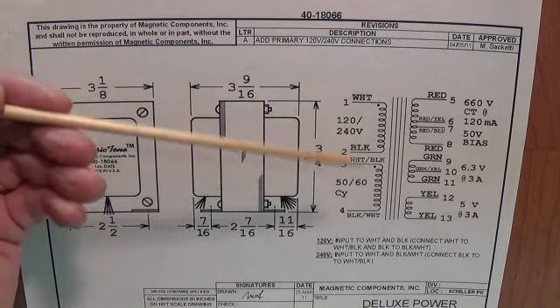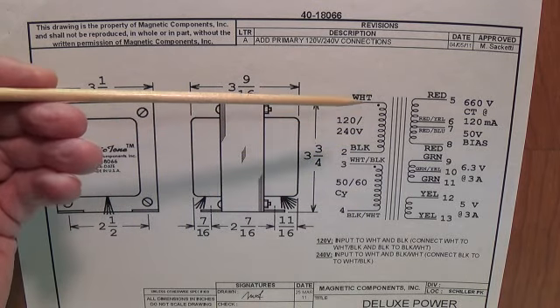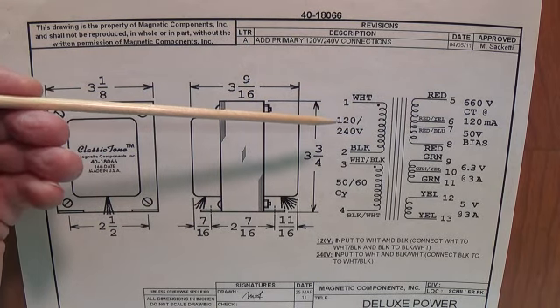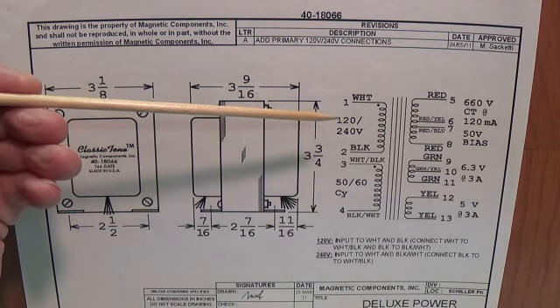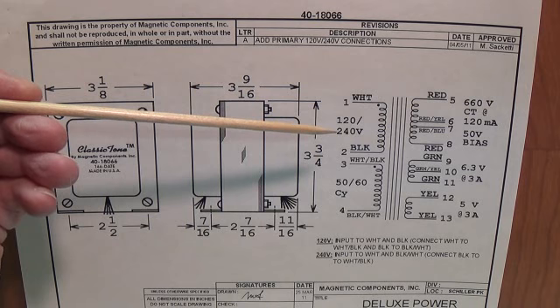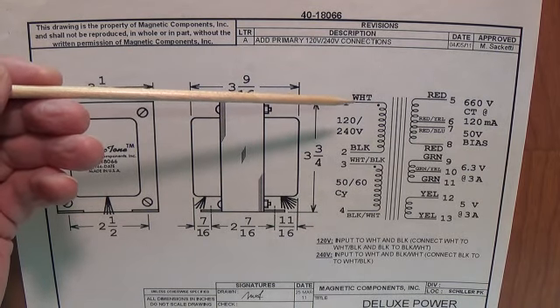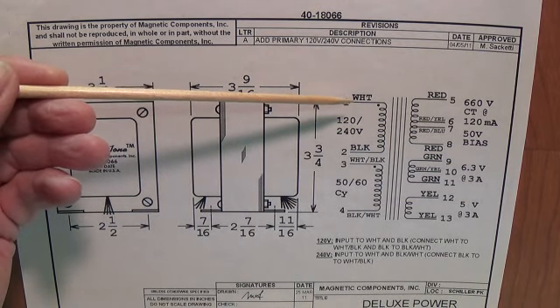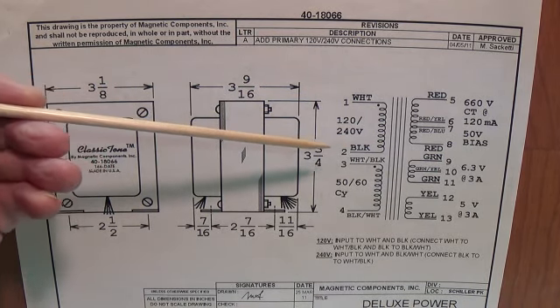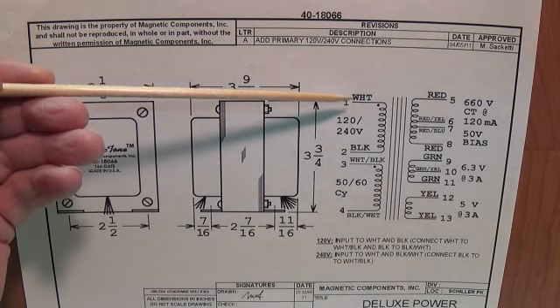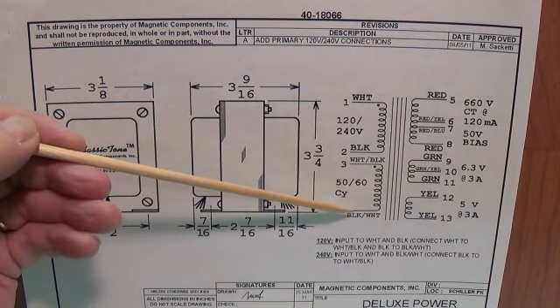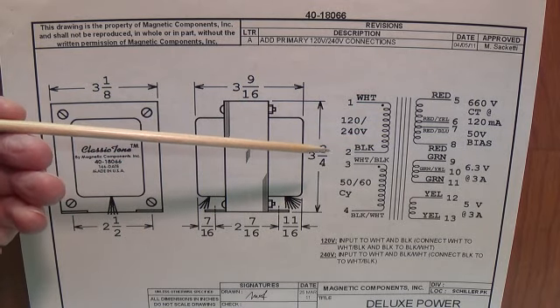First thing I notice is the primary of this recommended transformer is more complicated. And then I take another look here and I see that it's because it's suitable for both 120 volt AC and 240 volt AC. If you're going to use this transformer in the United States with 120 volts, you would use the white and black wires as your primary connections. If you were going to use this in Europe, you would connect to the white and the black-white as your primary connections, and then connect these 2 wires together so that the 240 ran all the way through both windings instead of through only one of the windings like the 120.